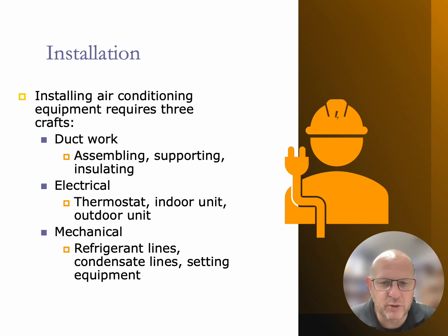depending on the location that you are, which state that you are in. You might be running the high voltage, or local codes might prohibit you from opening up the electric box. But for most of rural America, you will be opening up the electric box and hooking up the electric to the breaker box to run for the outdoor unit and also the indoor unit, especially on remodel applications or when you're replacing certain pieces of equipment that are out there.